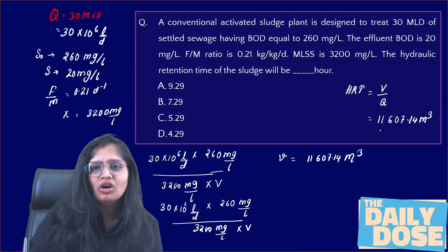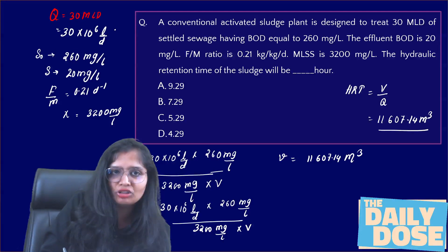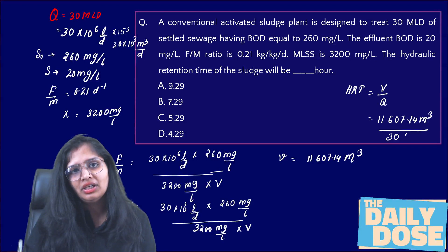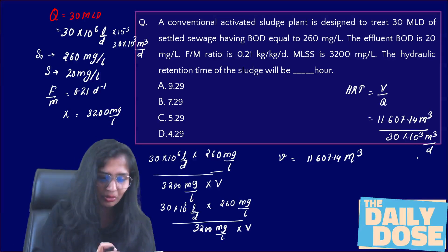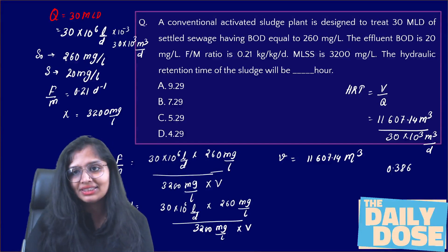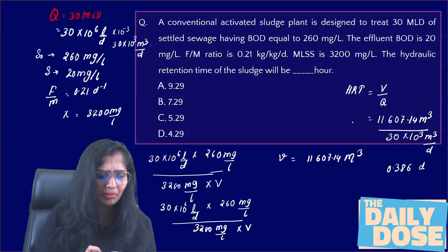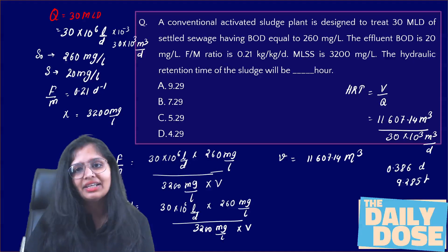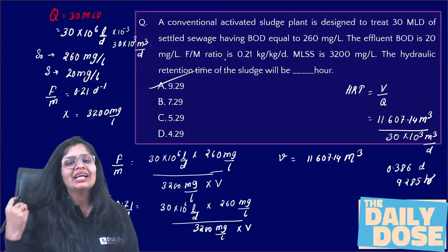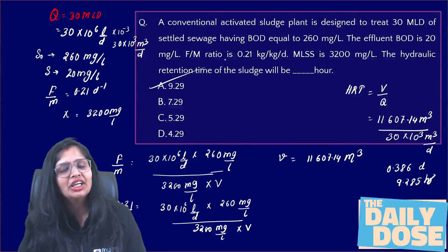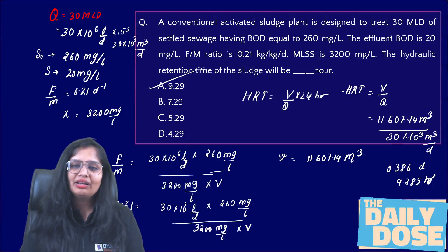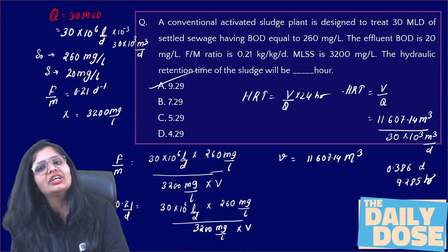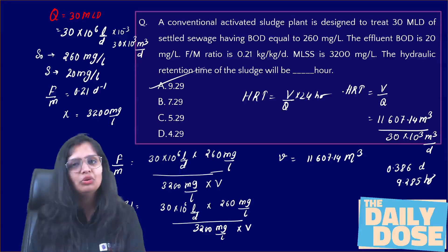Now the discharge is 30 × 10⁶ L/day, which equals 30 × 10³ m³/day. So HRT = Volume / Q = 11,607.14 / (30 × 10³) = 0.386 days. To convert to hours, multiply by 24, giving 9.285 hours, approximately 9.29 hours. In some books the formula is written directly as V/Q × 24 to get hours, since the day value is in decimals. So keep the formula V/Q × 24.